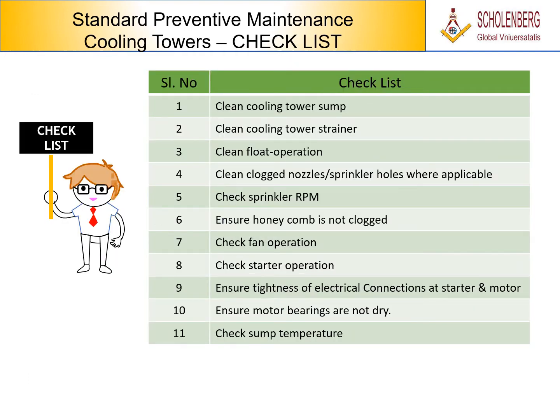Cooling towers, checklist. 1. Clean cooling tower sump. 2. Clean cooling tower strainer. 3. Clean float operation. 4. Clean clogged nozzle/sprinkler holes where applicable. 5. Check sprinkler RPM. 6. Ensure honeycomb is not clogged. 7. Check fan operation. 8. Check starter operation. 9. Ensure tightness of electrical connections at starter and motor. 10. Ensure motor bearings are not dry. 11. Check sump temperature.